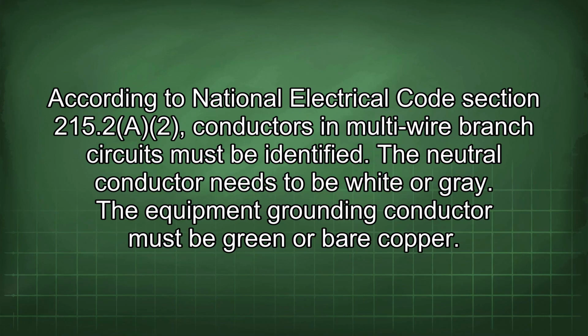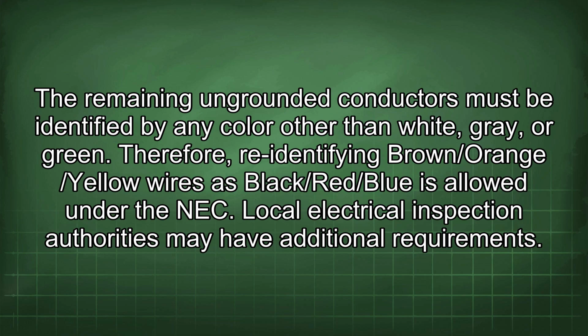According to National Electrical Code Section 215.2(A)(2), conductors in multi-wire branch circuits must be identified. The neutral conductor needs to be white or gray. The equipment grounding conductor must be green or bare copper. The remaining ungrounded conductors must be identified by any color other than white, gray, or green. Therefore, re-identifying brown/orange/yellow wires as black/red/blue is allowed under the NEC.